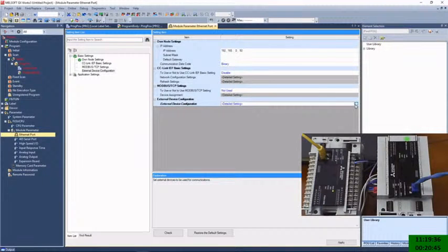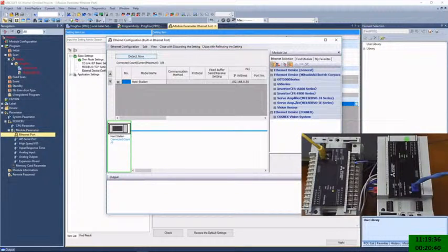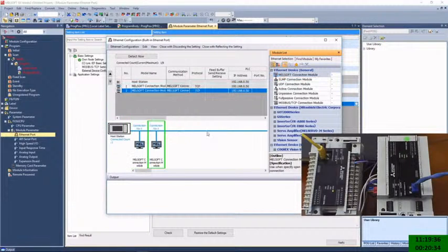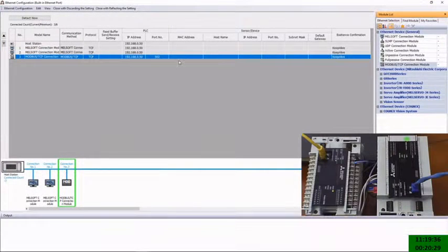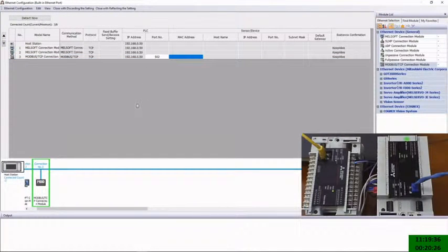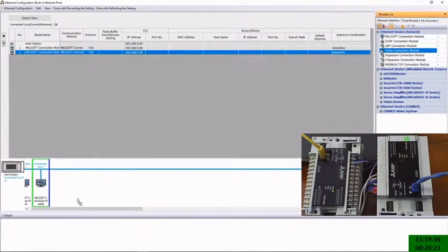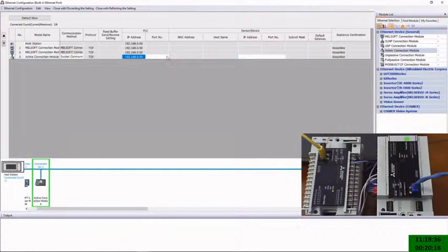And then I need to add the connections again as well, the external connections. First two connections I made was for MELSOFTs. That's for example if you want to have a SCADA connect to it. And then I created, oh, that's wrong. I think I added the wrong one over there. So you don't add the Modbus-TCP one, you add the active connection because it basically creates an open connection to it. My port is 5645, and then we are talking to their IP address, .55, with a local port number of 502.